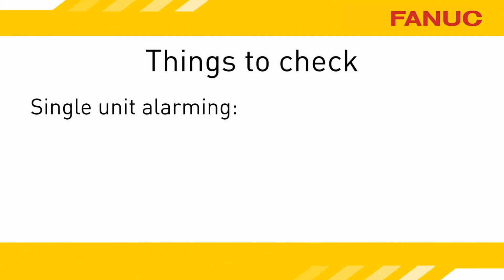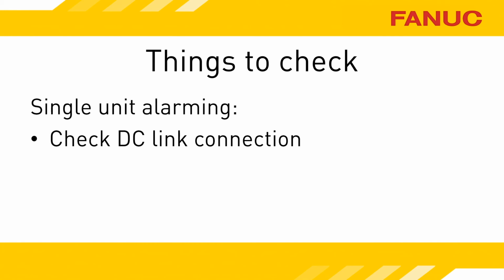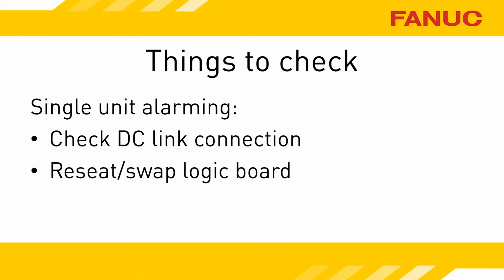In summary, if you're getting this alarm and it's only happening on one unit, make sure the DC link bus bars are securely attached to the amplifier. Reseat the gray logic board. If you have other servo amplifiers with the same part number, the logic board is the same, so you can swap it. Bear in mind, you run the risk of losing home position when you unplug feedback connectors. They're the ones with JF in the name.